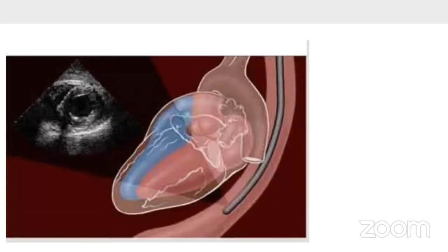It's rarely used now. Coming to the implantable cardioverter defibrillator, it provides anti-tachycardia and anti-bradycardia pacing, synchronous cardioversion or non-synchronous defibrillation shock, telemetry, and diagnostics, including the stored event electrograms and history logs. Pacing functions are all incorporated with the pacer, cardioverter, defibrillator also.